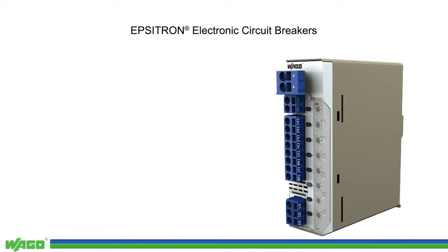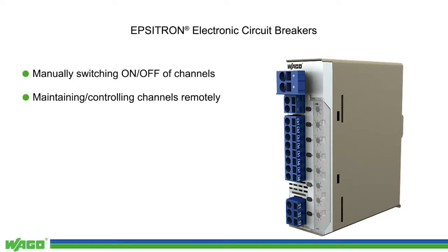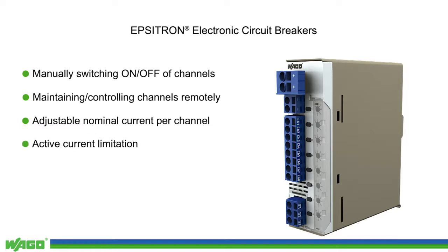WAGO's ECBs provide multiple functionalities, guaranteeing reliable, intelligent, and highly effective protection for your systems. All ECBs feature manually operated channels, allowing one or more channels to be switched on or off. The signal outputs enable remote status diagnostics for each individual channel. Furthermore, individual adjustability guarantees extremely precise tripping operation. Active current limitation prevents the power supply from switching to overload operation, preventing a voltage drop.